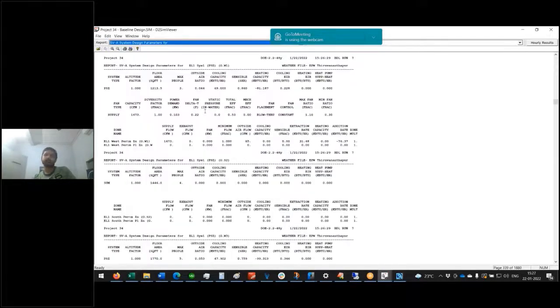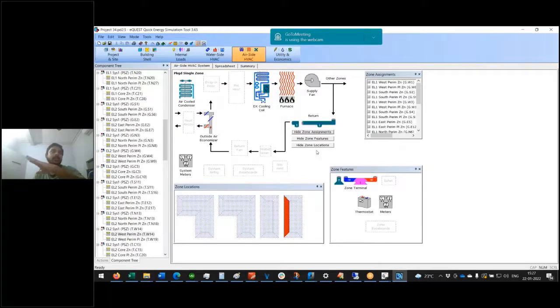So as you can see, some of the major ones have reduced. So it's very likely the case of undersizing. You can go up to about 2 CFM, and most of your throttling range should get controlled. If you put 2 CFM, ideally you shouldn't do it for everything, all the systems. Maybe 1 or 2 systems you could do it. That's perfectly okay. Sometimes it happens because the software is not perfect. So that's perfectly allowable legally as per the code. There's nothing barring you from doing that.